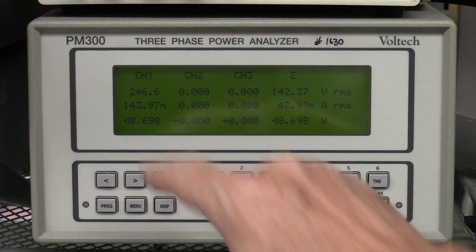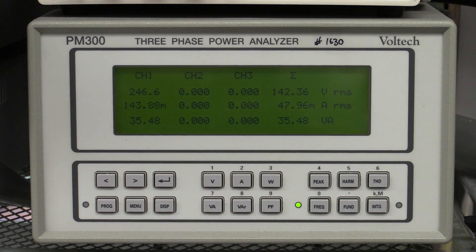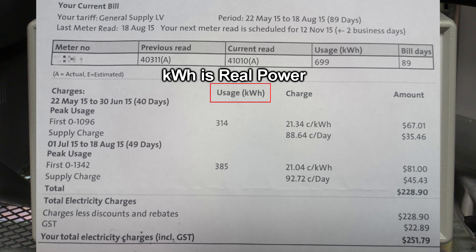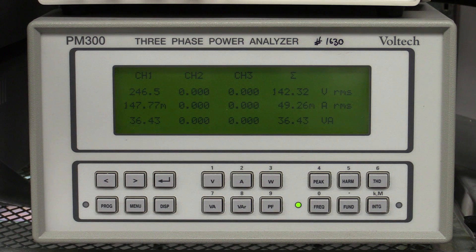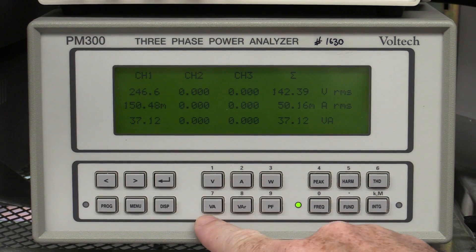VA, because look, if we have a look at this, this is apparent power, and sure enough, it's drawing a lot more apparent power. But unless your electricity bill says you're being charged in VA, then you're not being charged for this power factor, so even if this thing worked and corrected your power factor, you're not being charged for it, so you don't save a damn cent.